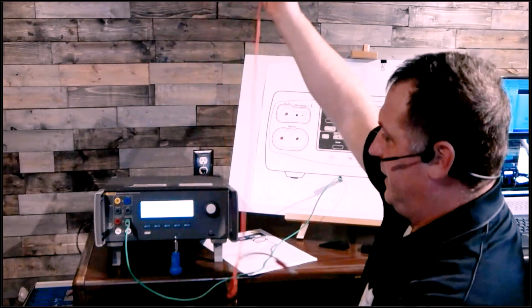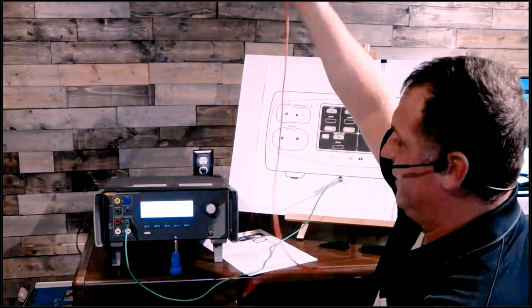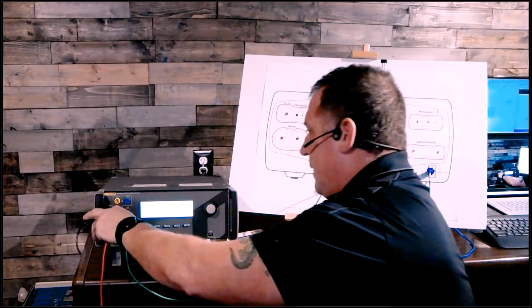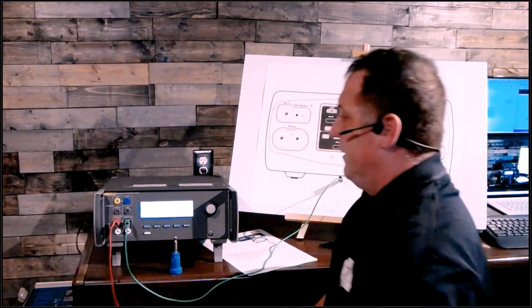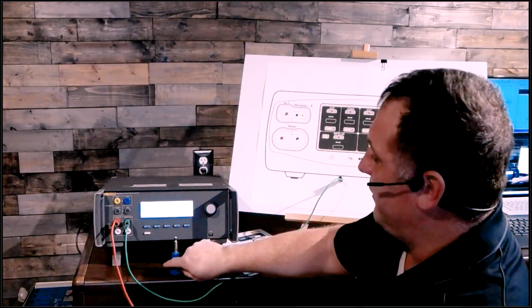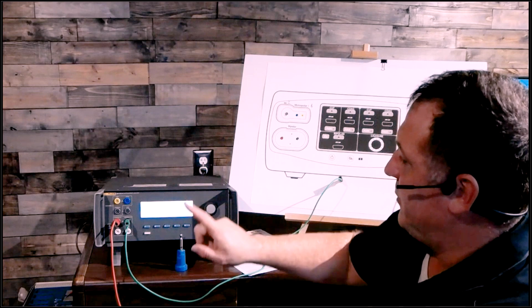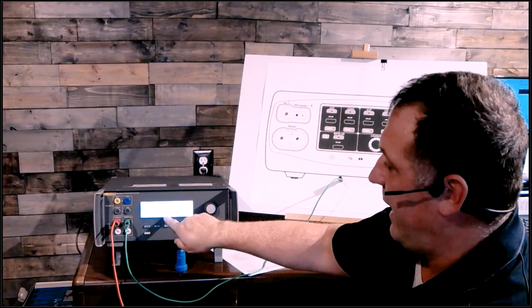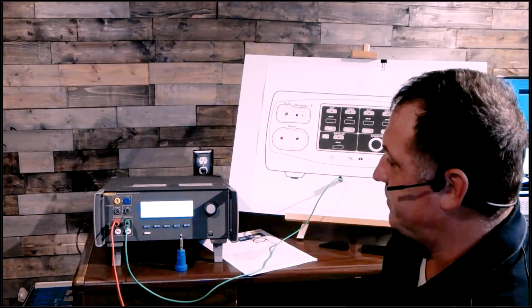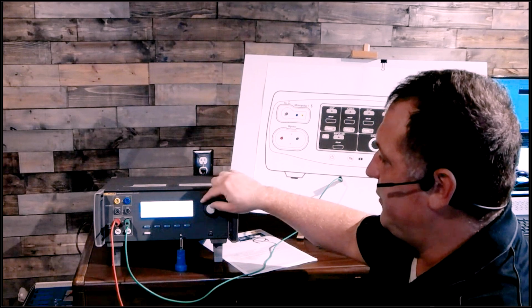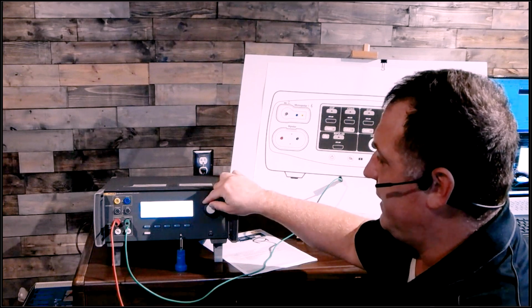Next, I'll take a red cable and connect it into the variable high of my ESU. On my QA-ES3, I'll go to HF leakage, high frequency leakage, F3. It'll automatically put a 200 ohm load on my QA-ES3. Then I'll look into my service manual and test all the outputs of my ESU at max output, worst case scenario.